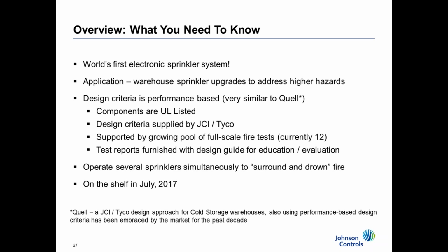The design criteria is very performance-based. So if you're familiar with Quell, which is a solution we offer for cold storage fire protection, we have components which are UL listed, but the design criteria that strings them together is provided by us. We've conducted multiple fire tests, of course, and this data will be provided to you as you're working on a project, and we work with you to support these discussions with the fire marshal, the AHJ, and we go from there. And really, like I said, the bigger concept here is surrounding and drowning the fire.